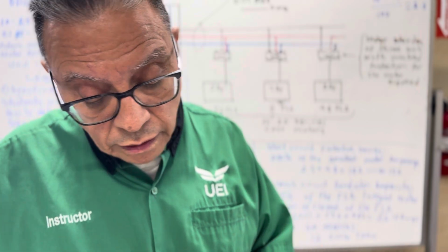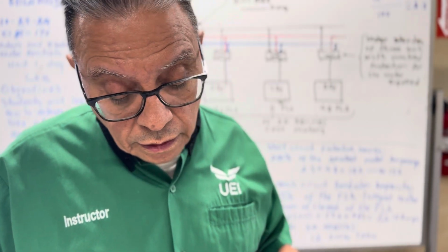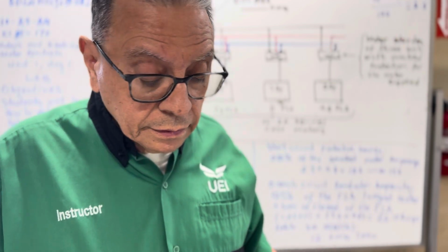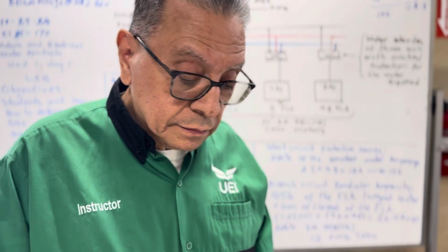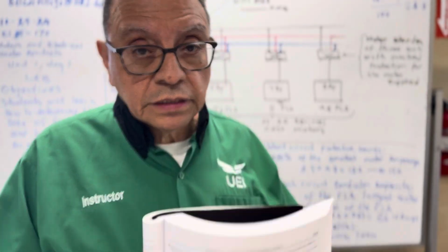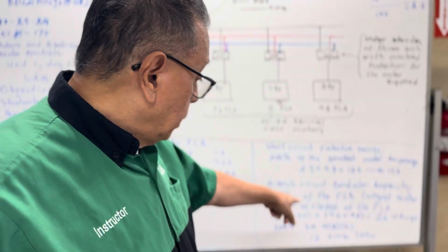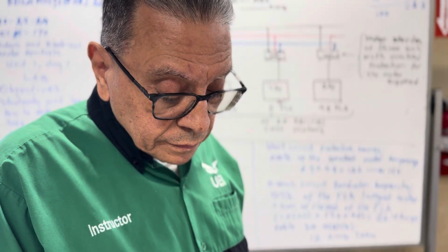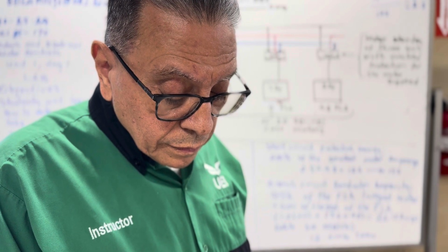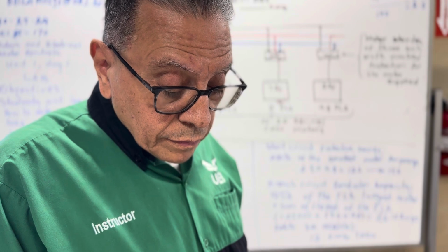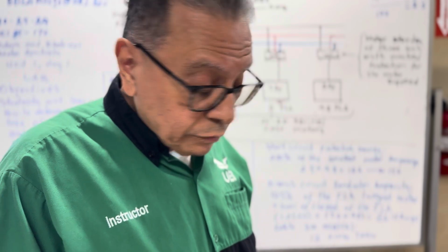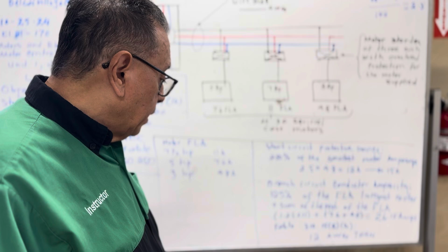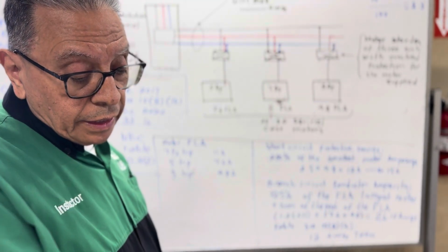Table 310.16, that is the table. So for 26 amps, I use gauge 12.